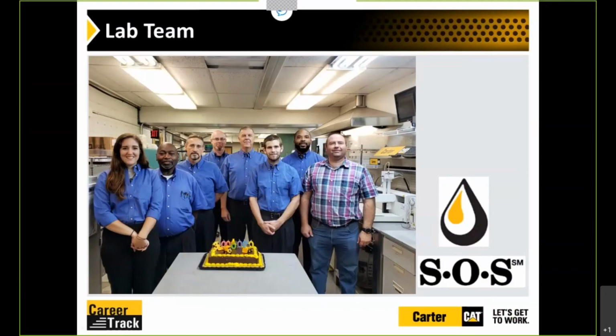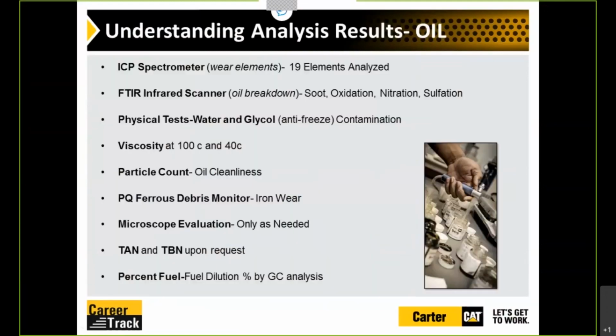And you might ask, well, what in the world do we test for when we're in the lab? For oil, we run a variety of analysis on it. We do ICP spectrometer. This is where we're looking for the wear elements. That's your irons, your coppers, your chromes, aluminums, things of that nature. We test 19 elements. We do FTIR, that's infrared analysis, your oil breakdown, where we're looking for soot and oxidation, nitration, sulfation. We do physical tests where we're looking for water, fuel, glycol, things of that nature.